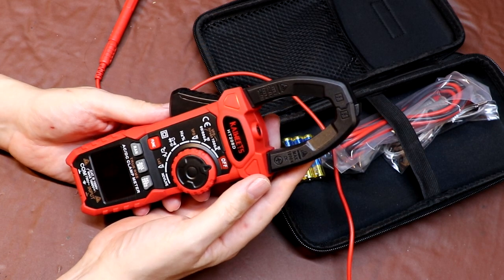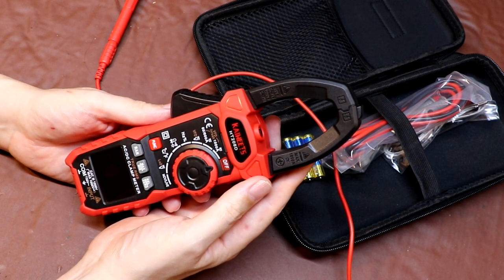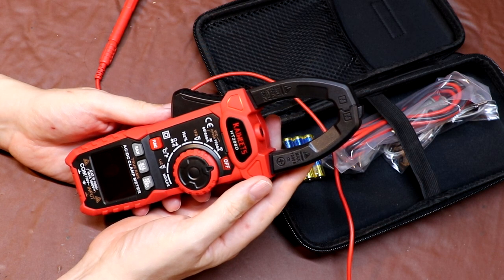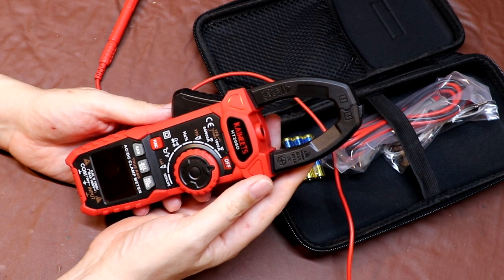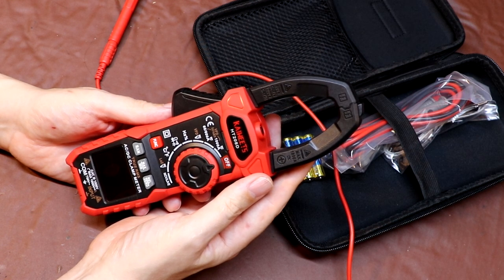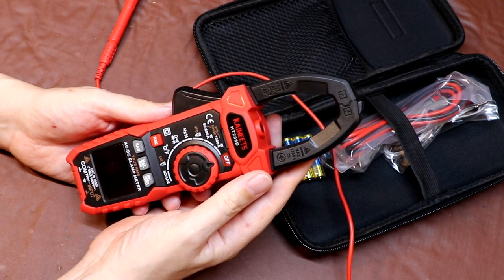Now for working in domestic situations, we don't really encounter very high currents or circuits that can supply very high currents. Typically our plug sockets have a maximum of 13 amp fuse in it. Those plug sockets will be protected in themselves by something like a 32 amp circuit breaker, and in fact the whole supply to my house is protected from a 100 amp fixed fuse. So the most current you could really expect to see is something in the region of a few hundred amps. But if you were to go into an industrial situation with large control panels, the actual fault currents can be in the thousands of amps.